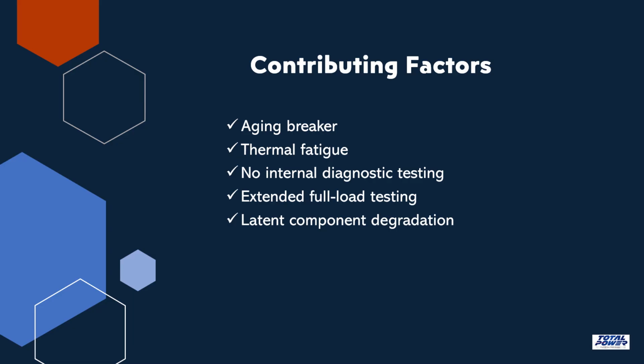Another contributing factor was the sustained electrical loading associated with a 2-hour load bank test. Although the breaker was designed for these conditions, prolonged thermal loading accelerated the failure of an already weakened component. Most importantly, no evidence suggested the crew caused the failure. The investigation demonstrated the value of looking beyond immediate causes to identify weaknesses within equipment management systems.